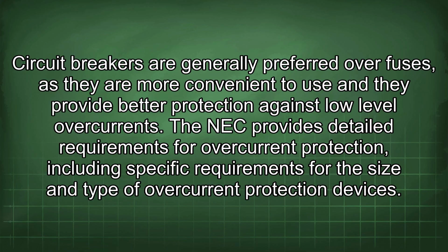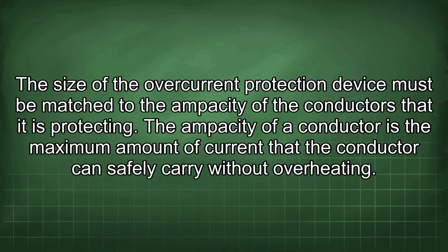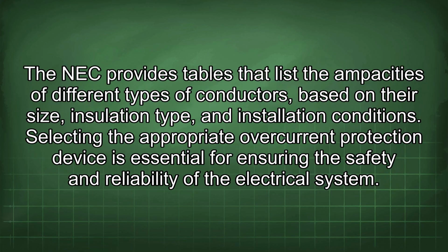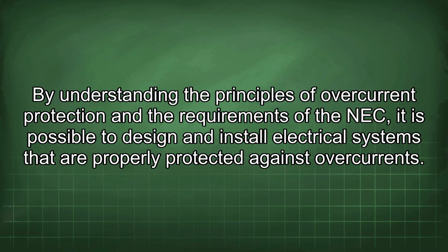Circuit breakers are generally preferred over fuses, as they are more convenient to use and they provide better protection against low-level overcurrents. The NEC provides detailed requirements for overcurrent protection, including specific requirements for the size and type of overcurrent protection devices. The size of the overcurrent protection device must be matched to the ampacity of the conductors that it is protecting. The ampacity of a conductor is the maximum amount of current that the conductor can safely carry without overheating. The NEC provides tables that list the ampacities of different types of conductors based on their size, insulation type, and installation conditions. Selecting the appropriate overcurrent protection device is essential for ensuring the safety and reliability of the electrical system. By understanding the principles of overcurrent protection and the requirements of the NEC, it is possible to design and install electrical systems that are properly protected against overcurrents.